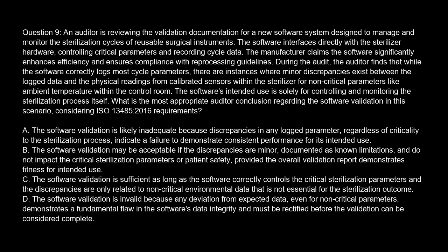Option A. The software validation is likely inadequate because discrepancies in any logged parameter, regardless of criticality to the sterilization process, indicate a failure to demonstrate consistent performance for its intended use. Option B. The software validation may be acceptable if the discrepancies are minor, documented as known limitations, and do not impact the critical sterilization parameters or patient safety, provided the overall validation report demonstrates fitness for intended use.